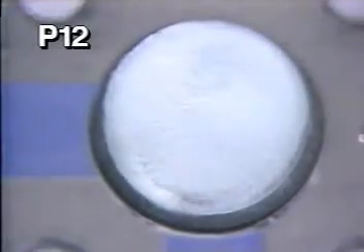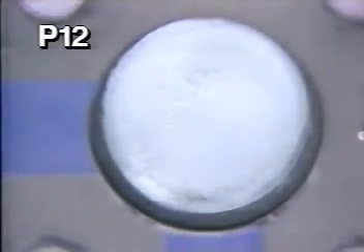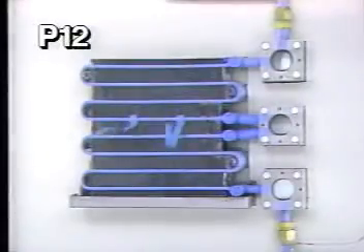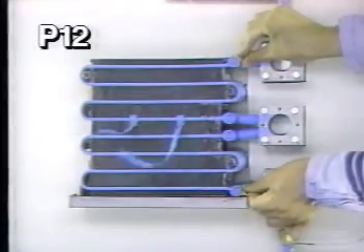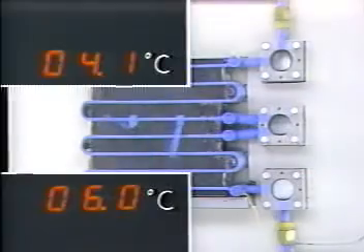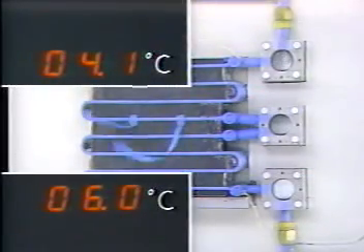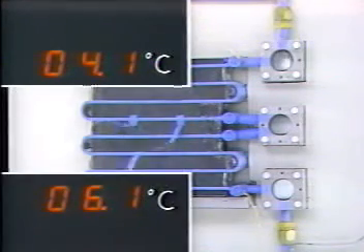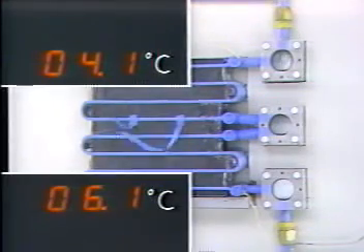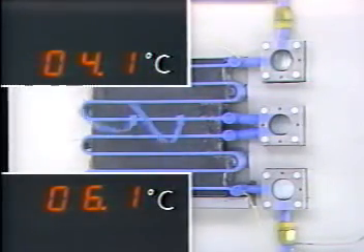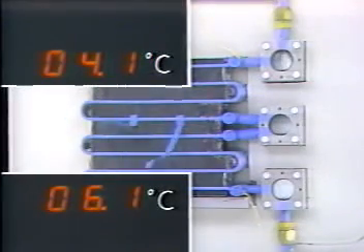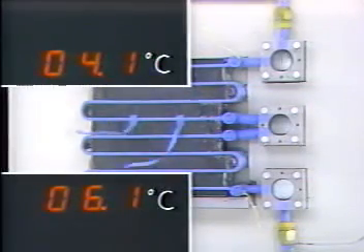This is the refrigerant at the exit of the evaporator. The liquid has disappeared, and the exit is filled with a gasified mist. In other words, the refrigerant has evaporated completely. Let's compare the temperature at the entrance and at the exit of the evaporator. The temperature of the refrigerant is 4 degrees centigrade at the entrance and 6 degrees centigrade at the exit. Assuming that the temperature of the ambient air near the evaporator is 40 degrees centigrade, the air temperature is lowered by 36 degrees near the entrance and by 34 degrees near the exit by the evaporation of the refrigerant.